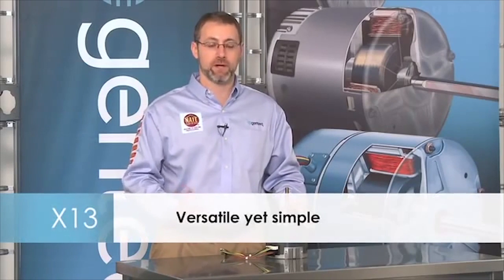So what we've learned so far is that the X13 is versatile, but it's also very simple to work on. We will need the OEM manuals that go with the appliance that an X13 is used in so that we know what tap to use for the right airflow for each heating, cooling, and fan demand in the system. X13 is ECM technology made easy.